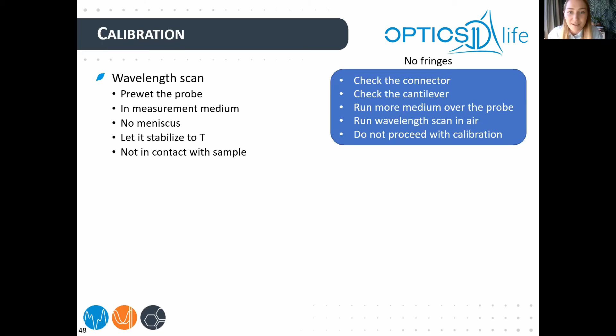If you still don't have any signal, then you can take out the probe, dry it, and run the wavelength scan in air and see if there is a signal. If there is a signal in air, then there should be a signal in liquid as well, so there's something wrong with the medium or with entering into the medium. If you still don't have any signal in the wavelength scan, do not proceed with calibration because you will break the probe. So these are my tips.